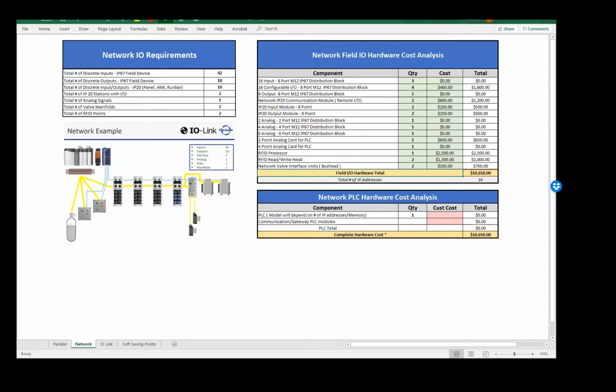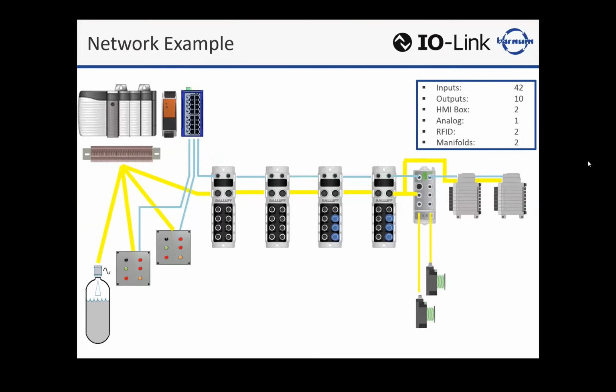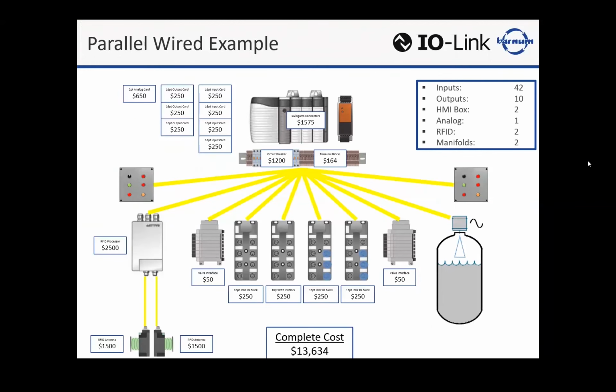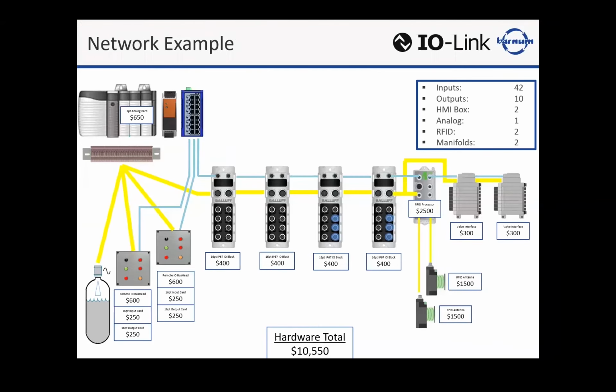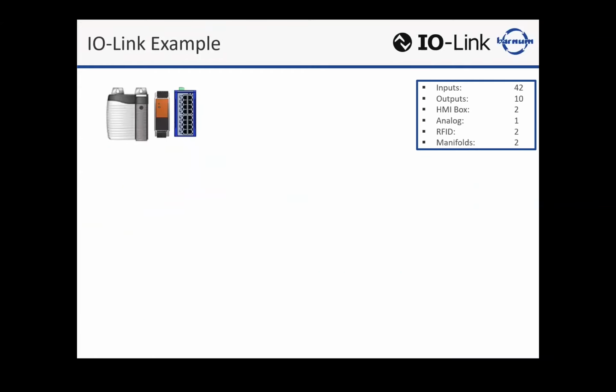Perfect. Let's go back to our layouts and do an IO-Link comparison. First of all, here's our cost as it was for parallel wiring, and here's our cost for our network wiring as it lays out. So how do we do the IO-Link? So IO-Link, again, we're going to keep the same network requirements. So if you start dropping it in there, John. Yep. So what's the main component of IO-Link? Yeah. So here's where the model is going to change.